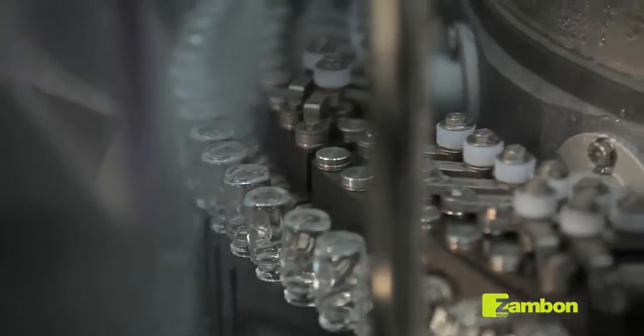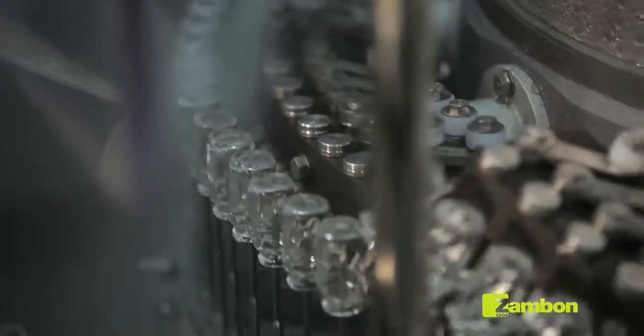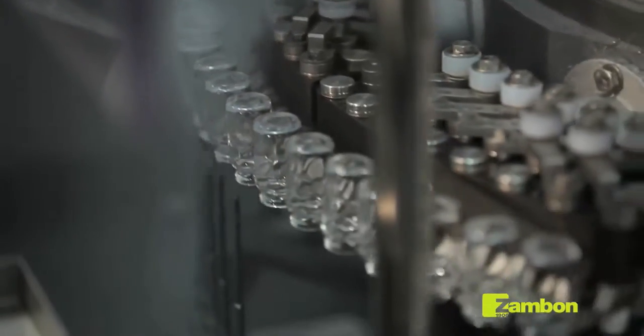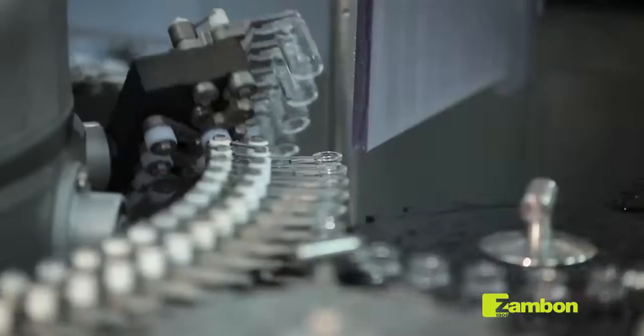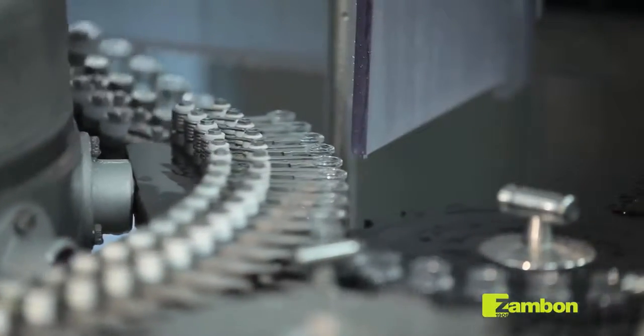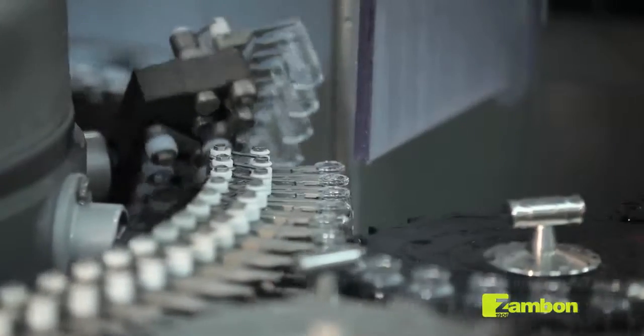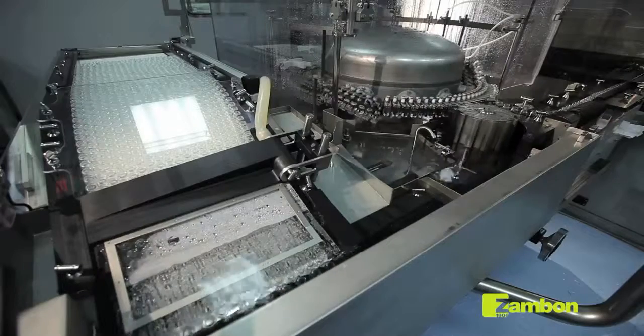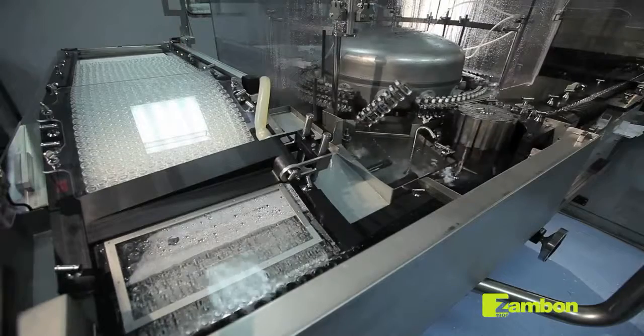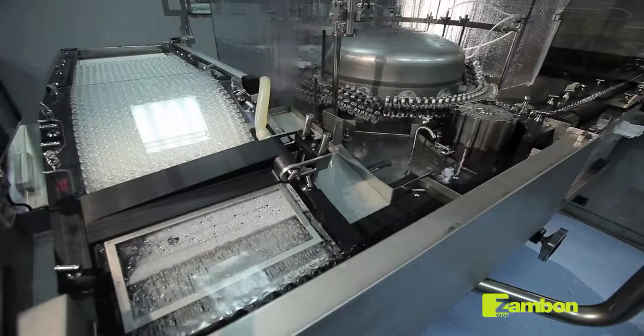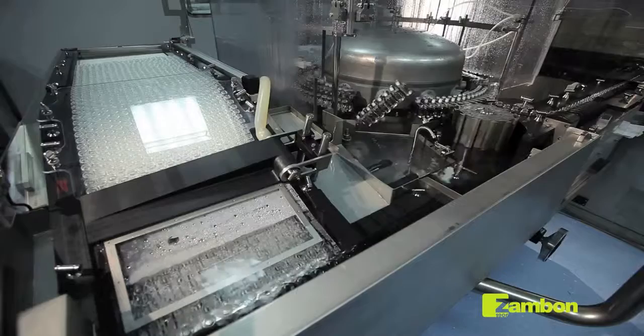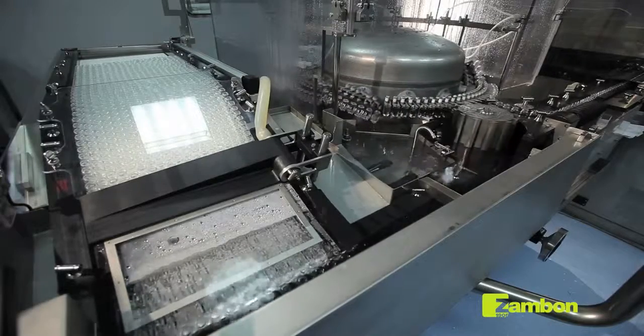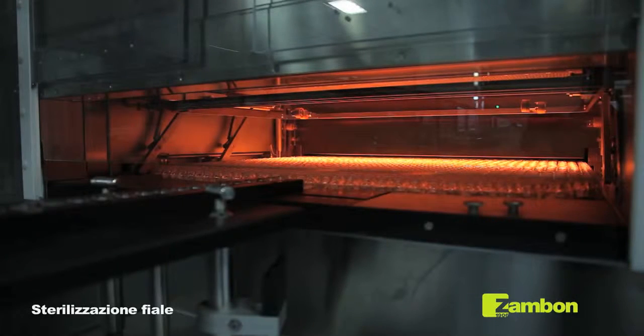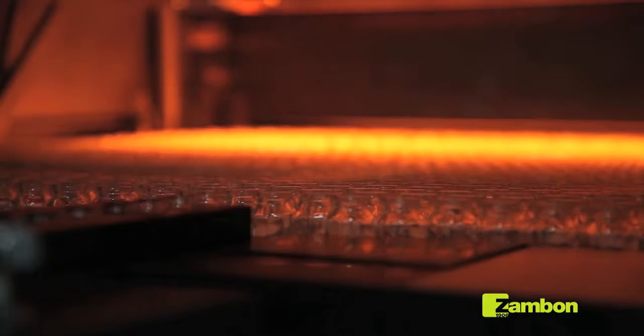Any materials which are not sterilizable at 121 degrees Celsius are sanitized with chemical agents such as hydrogen peroxide in another machine called a pass box, where they undergo a sanitization cycle before being transferred inside the clean room. Once washed and dried, the bottles are fed automatically into the sterilization tunnel, where they reach a temperature of at least 300 degrees Celsius for the time needed to guarantee their sterilization.